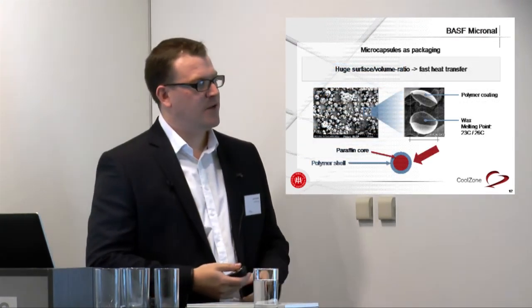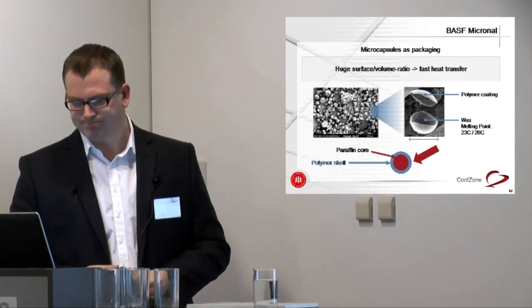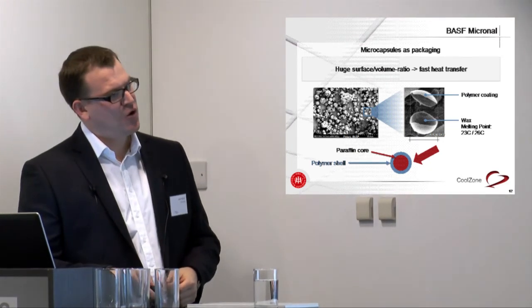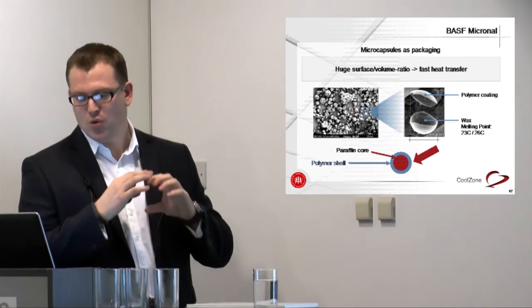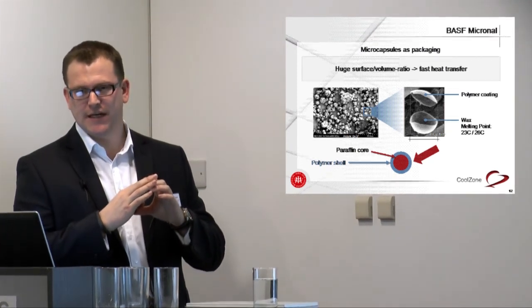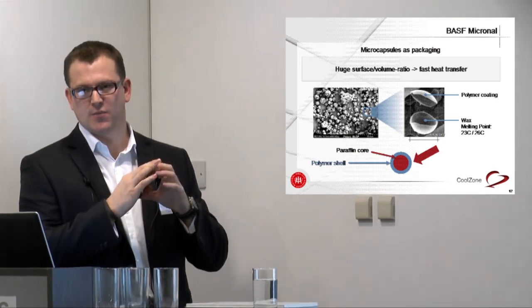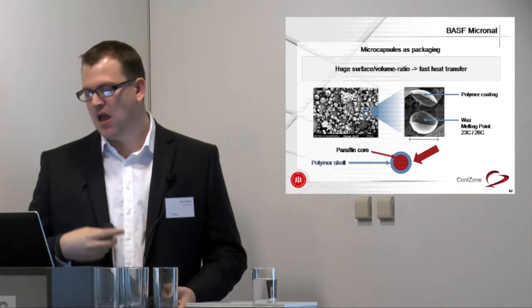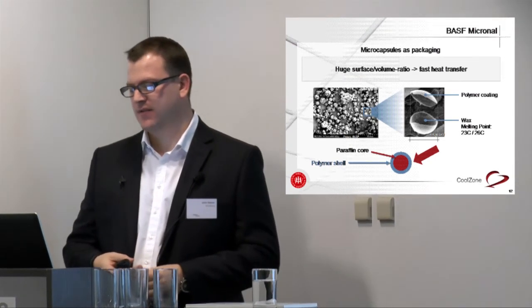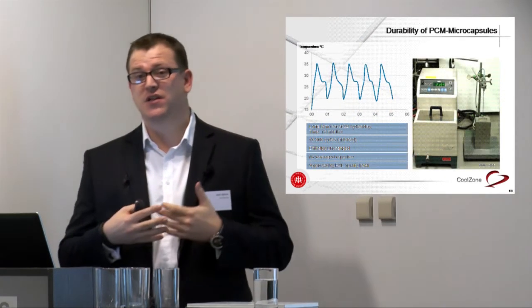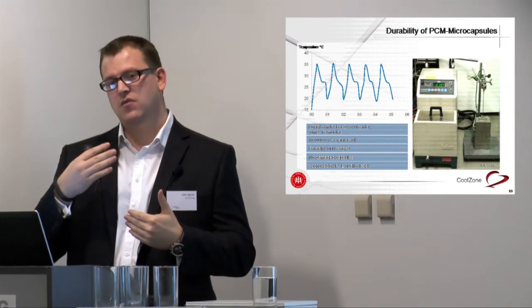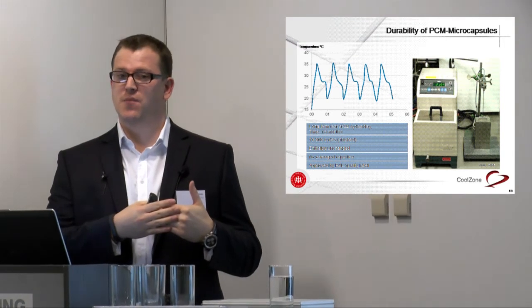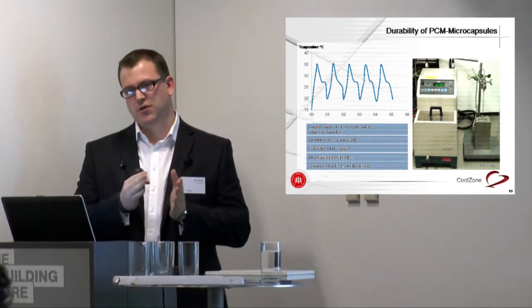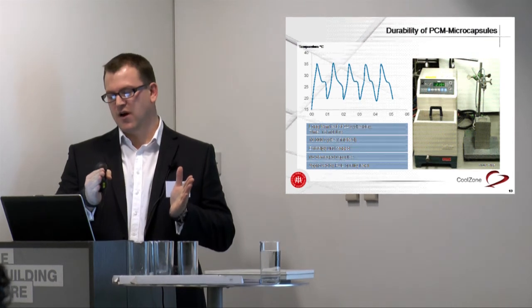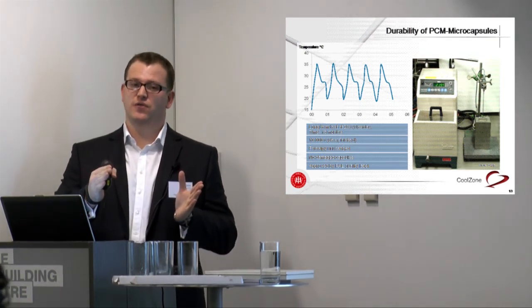This is what the wax capsules look like under a microscope. You can see the paraffin core and the protective shell, which keeps the melting and solidifying contained in one space so the product can't leak out. We have a couple of set points for the melting point, 23 degrees or 26 degrees. For Cool Zone we use 23 degrees, meaning the room may reach 24 or 25 degrees before the heat gets through and starts melting the product. So we're looking at around 25, 26 to 28 degrees as the useful zone for managing overheating.